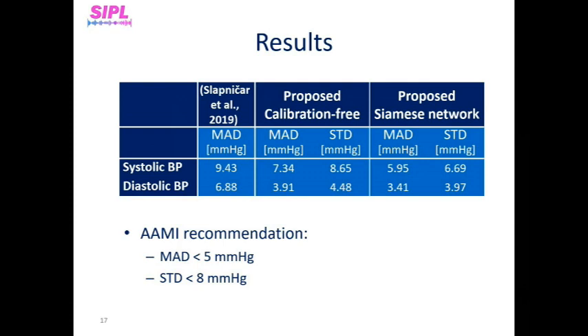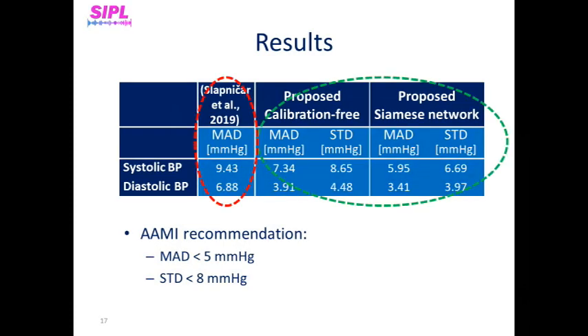The Association for the Advancement of Medical Instrumentation recommends that the mean absolute difference of non-invasive blood pressure measurement should not exceed 5 mmHg, and the standard deviation should not exceed 8 mmHg from a reference method. With calibration, we meet this requirement for diastolic blood pressure and almost meet it for systolic blood pressure. Even without calibration, the accuracy achieved is very promising. Unlike other methods, as can be seen in the left column, our results are significantly more accurate, and we can say that finally we have obtained satisfactory results that are feasible for home applications.